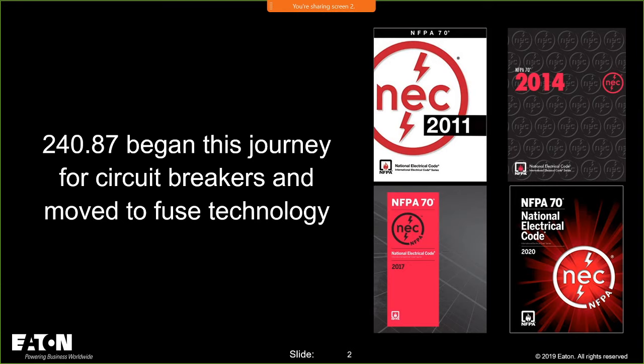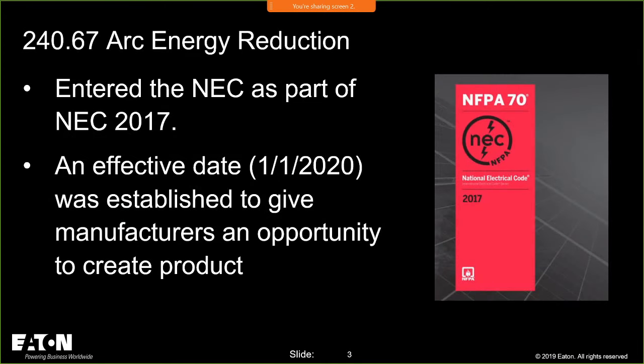2011 is when it went into the National Electrical Code, and it continued to be refined. And it was in the 2017 version of the NEC that they said, hold on, we're doing all of this on circuit breakers for these large breakers that have a large delay. In fact, the requirement in 240.87 started with circuit breakers that didn't have an instantaneous, and I call those the double wides. Those are the big boys, and we don't sell that many of those out there. But it's not just the breakers that don't have an instantaneous that present a challenge. It's also those breakers that have 30 cycle time delays, which have an instantaneous and have a short time delay, but we just have to address the arcing currents, etc.